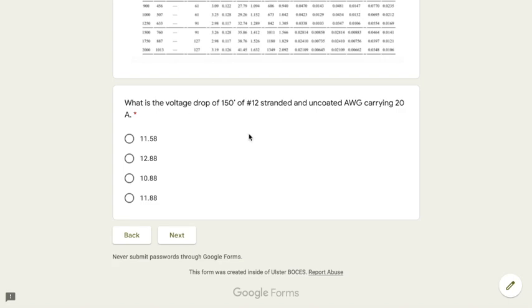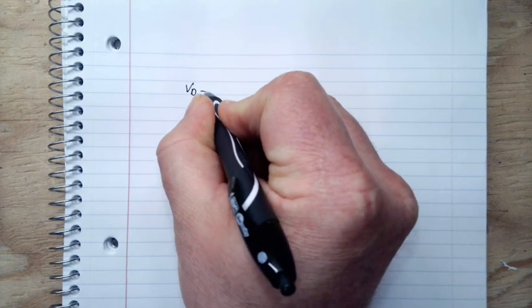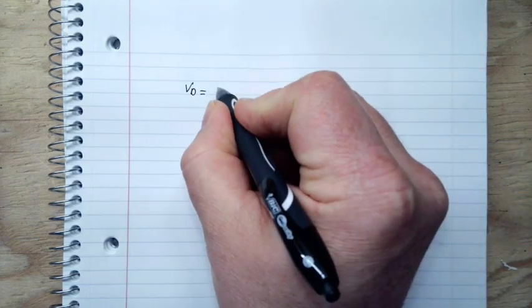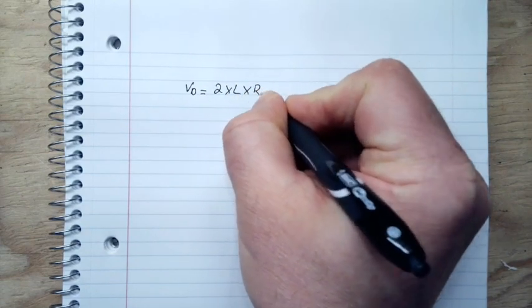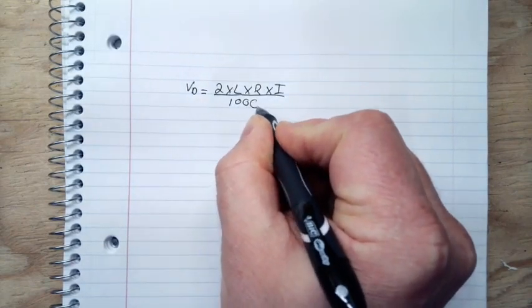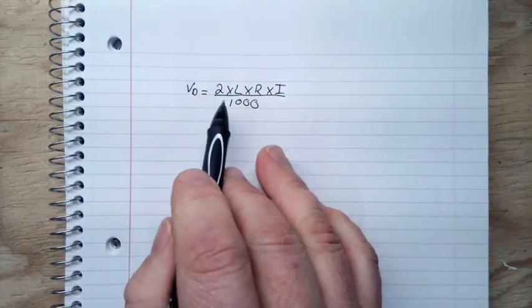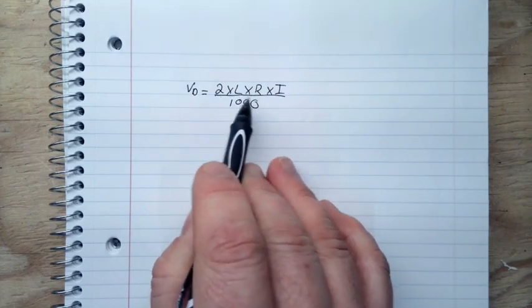The first thing we're going to need to know is the equation. Voltage drop, VD, is equal to 2 times L times R times I divided by 1,000. Again, that voltage drop is equal to 2 times the length times the resistance times the current divided by 1,000.